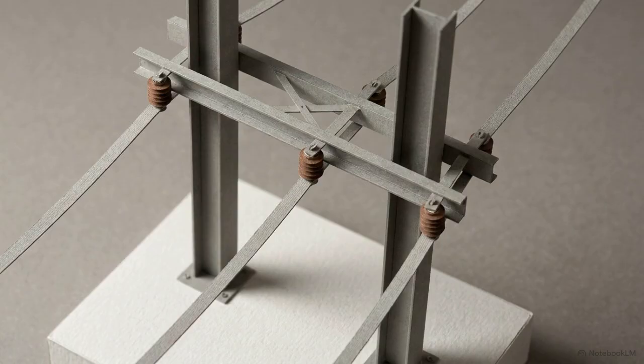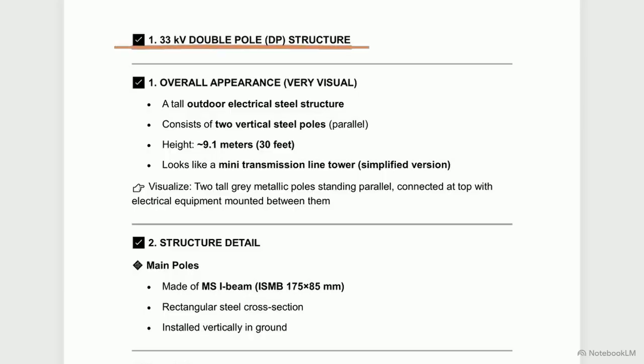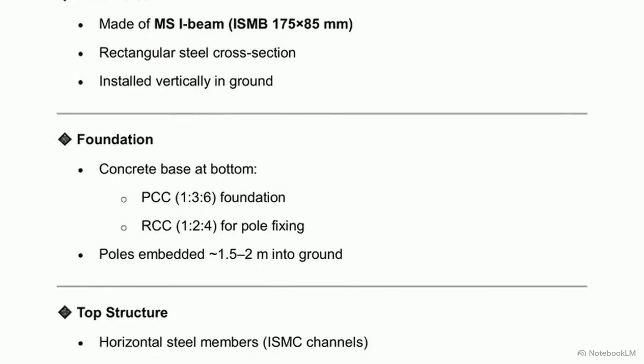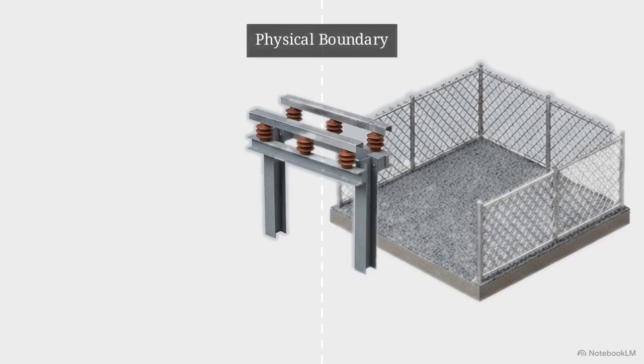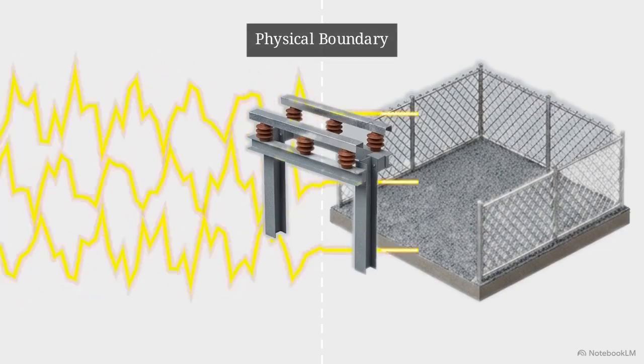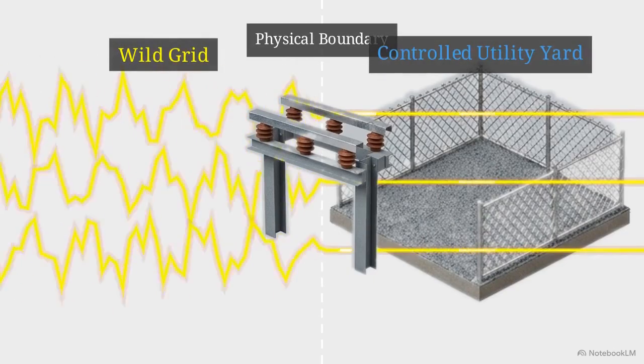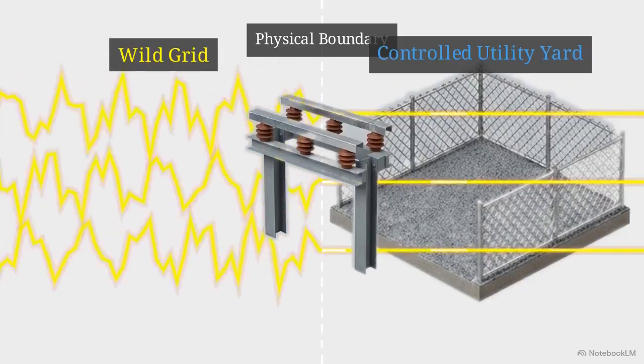The journey into the city begins at the intake tower. In the electrical world, this is the 33 kilovolt double pole structure, a 30-foot tall gateway. Looking at this specification sheet for the double pole structure, you can see it is built from two parallel steel I-beams. To safely hold back 33,000 volts of pressure, those heavy steel beams have to be deeply anchored into a solid concrete foundation. This tower marks the physical boundary line. It is the exact moment the electricity leaves the wild grid and enters a controlled utility yard.